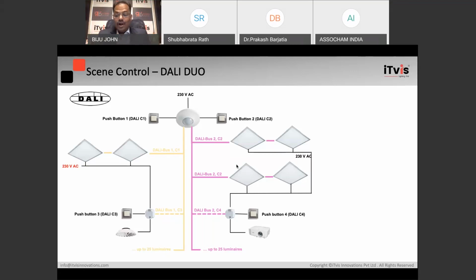And if you don't have that many as 50 DALI fixtures, you can take out certain DALI channels and use a DALI relay there and connect your projector. Use another DALI relay and connect your AC. Why DALI relay? Because this sensor communicates in DALI language, which is a protocol. And if the device doesn't have a DALI interpreter, it may not be able to accept the communication. So whenever you use a non-DALI device, use a DALI relay. The fixtures are DALI because you wanted dimming for that. Wow. One sensor more than enough for a wide area of office, a wide area of conference room.